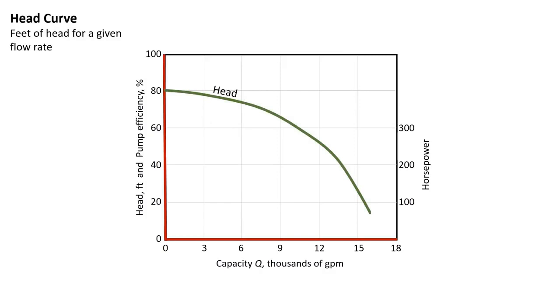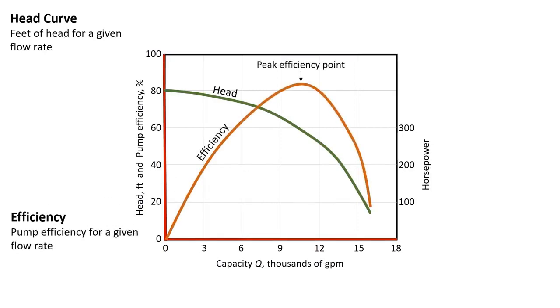Here we have a pump characteristic curve showing head in feet and pump efficiency versus the capacity in thousands of gallons per minute. Looking at the pump curve for a particular impeller, the head curve shows feet of head for a given flow rate. We also need to plot the efficiency curve for that impeller, which shows pump efficiency for a given flow rate. You can see that we have the peak efficiency point right at the top of the efficiency curve.